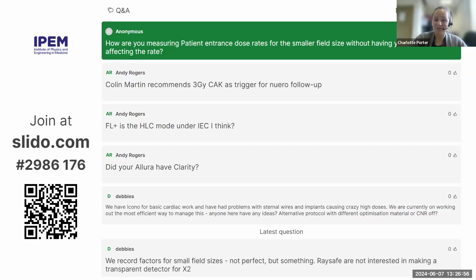We use an ionization chamber, so obviously we don't have a solid state chamber in the beam, but like Greg says, it does still impact it. So I guess you might want to add an extra column to your QA spreadsheet to say specifically which sensing area you're using, and think about ways of adjusting your work instructions to make it as repeatable as possible. But yeah, it's hard.